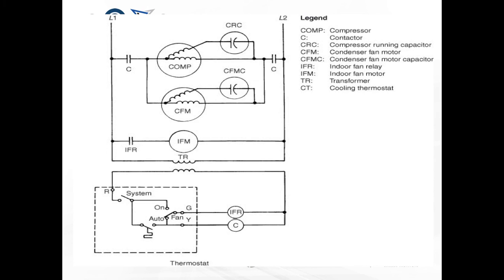This is just a slightly more complicated system. Again, it's a cooling system. We have several parts of this. We have our transformer down here. We have an indoor fan relay coil. We have a contactor coil. In our primary side, we have our indoor fan relay contact, which, by the way, matches initials to that coil. We have our indoor fan motor. Up here we have C and C, which are the contacts that connect that coil marked C. But you'll notice again, there's no electrical connection between the primary and the secondary side of the system.